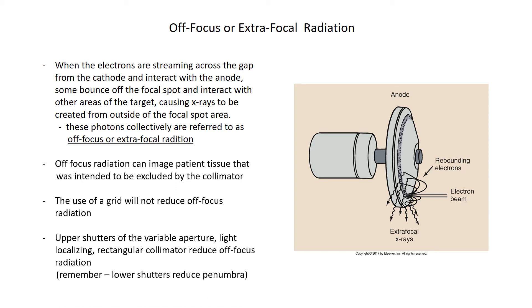To reduce off-focus radiation, use your variable aperture light-localizing rectangular collimator. Remember you have upper shutters and lower shutters — the upper shutters help reduce off-focus radiation, while the lower shutters help reduce penumbra.